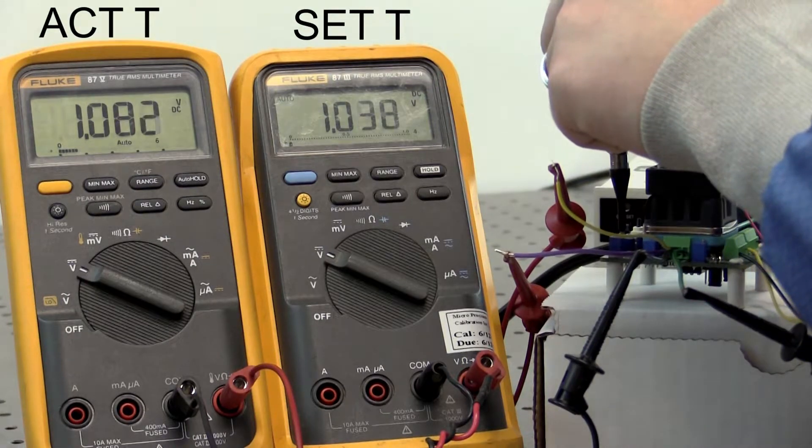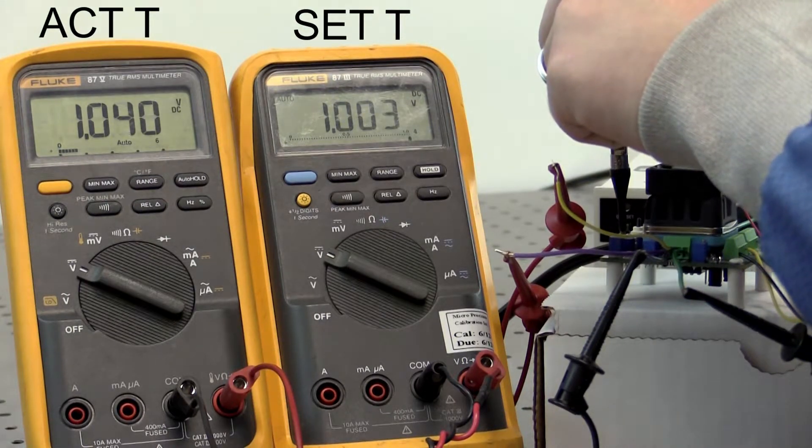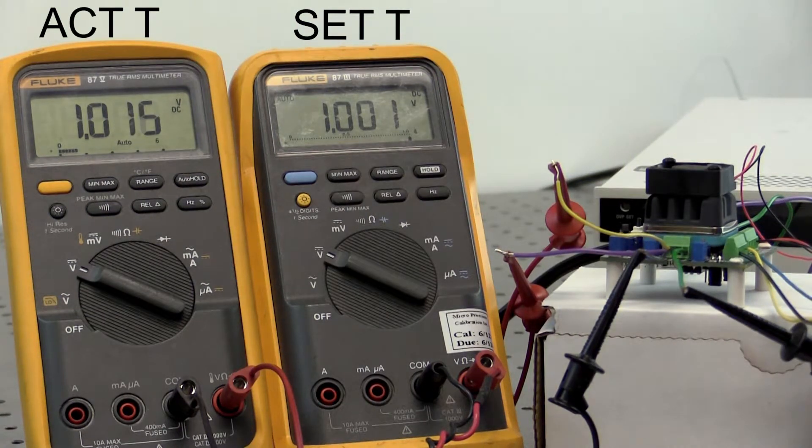To adjust the SET-T, with the voltmeter attached to the SET-T and COM wires, turn the SET-T trim pot screw. Rotate the trim pot clockwise to increase or counterclockwise to decrease the voltage.